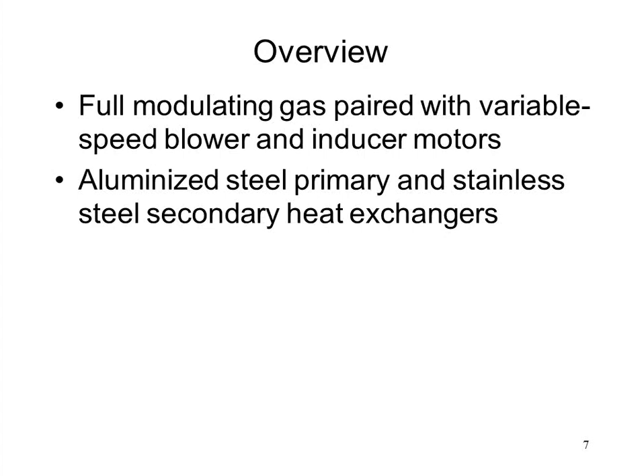So all three variables are in fact modulating, and that's one of the reasons why we need to have this system utilized with an Infinity touchscreen thermostat or an Evolution Connex thermostat. We don't run these modulating gas systems with a regular thermostat. They need to be operating with those communicating thermostats because there's going to be additional data that they need from the thermostat in order to function correctly. And we'll explain that here in a little bit.